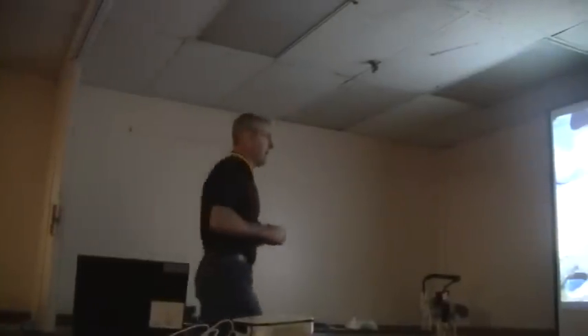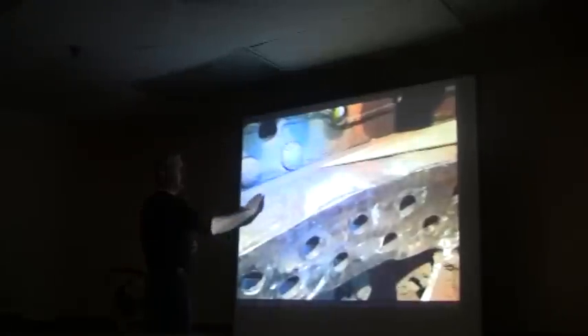Part of it is the erosive action of the water flowing around through there, especially if it's close to one of those blowdown valves. As you open that valve up, that water at 425 degrees, 300 psi is water. As you give it a path to the atmosphere, I mean, it is nearly supersonic in its path out. And it's taking with it all kinds of sediment and debris and other things, and over time it's going to erode the steel. So we've had to clean that up too, and you can't see it, but right in here we've cleaned that up. There were some pretty heavy pits, probably weren't the end of the world, but we've got it apart. So we're going to address that too.